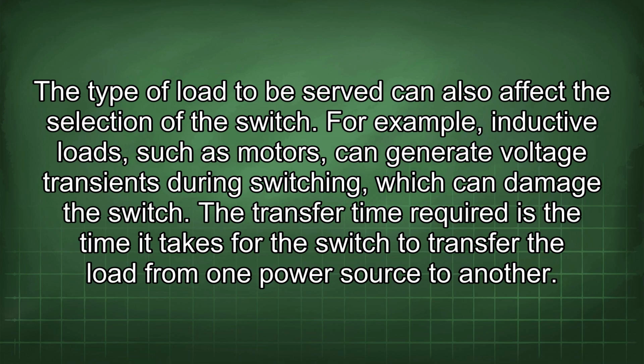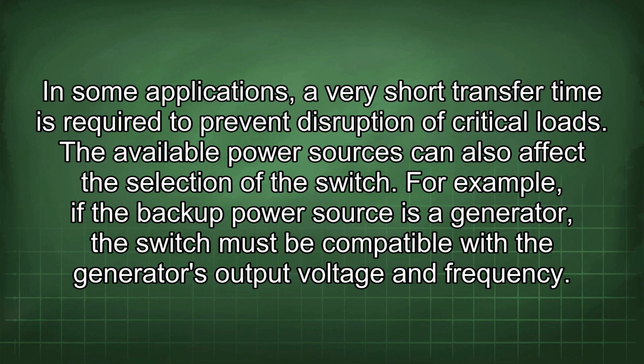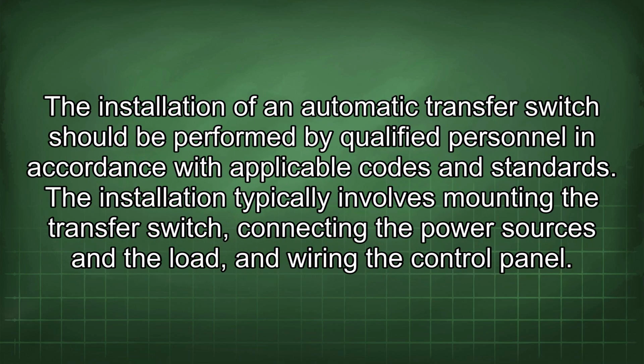The transfer time required is the time it takes for the switch to transfer the load from one power source to another. In some applications, a very short transfer time is required to prevent disruption of critical loads. The available power sources can also affect the selection of the switch. For example, if the backup power source is a generator, the switch must be compatible with the generator's output voltage and frequency.